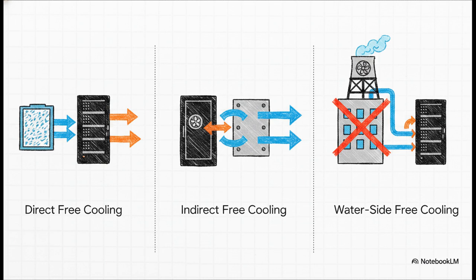Second is indirect free cooling. This one uses a heat exchanger. The cold outside air chills a metal plate, and that plate chills the inside air, keeping the internal environment perfectly sealed and sterile. And finally, waterside free cooling. This uses massive cooling towers on the roof to chill a loop of water with the outside air, directly bypassing the compressor. Because water holds heat so much better than air, this waterside method is actually the most stable and popular choice for massive modern data centers today.